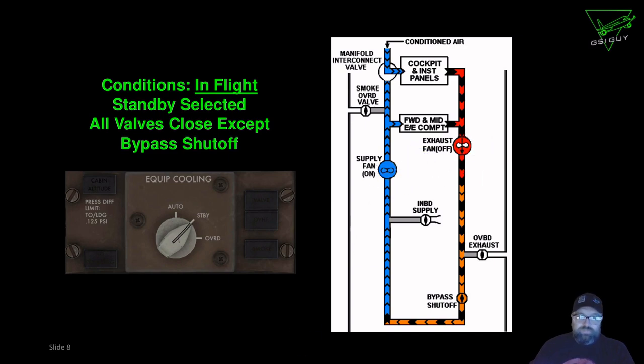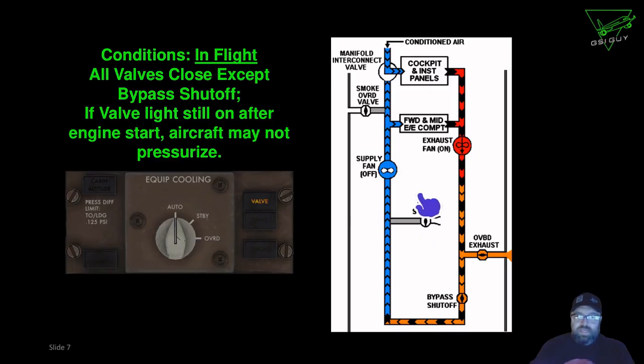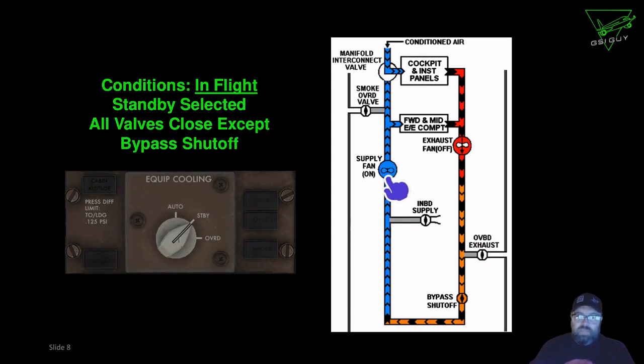It switches. So if we look here, right, supply fan off, exhaust fan on, supply fan on, exhaust fan off. Okay, so it switches my position of my fans as far as which one is operating and when, for that matter. But in this case, it fixed our problem, closes the valve, turns the light off, or extinguishes our valve light, right? And then switches our fans. So in this case, we can continue to operate in this setting and be perfectly fine. It's not going to be an issue.